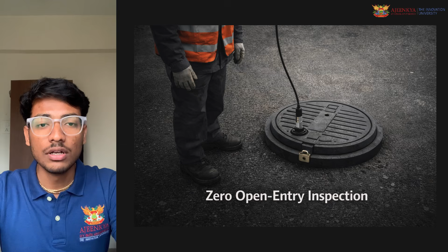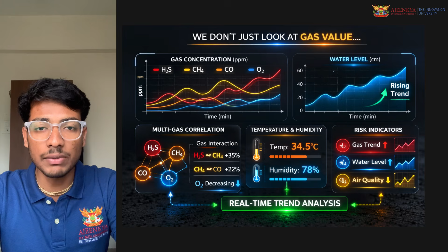But the important part is we don't just look at the gas value and check if it crossed the limit. We look at trends - is the gas rising fast? Is the water level slowly increasing? Are multiple gases changing together? So instead of a single number, we study the behavior over time.